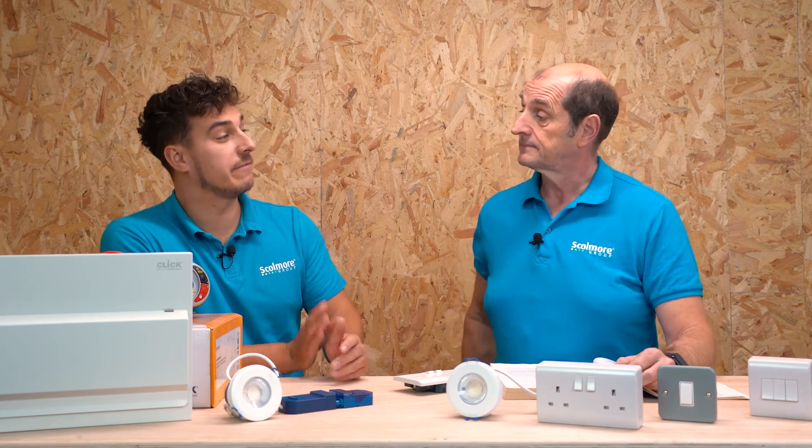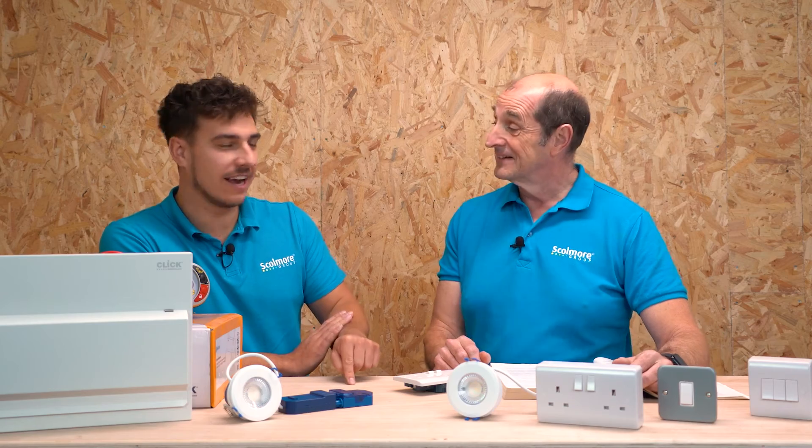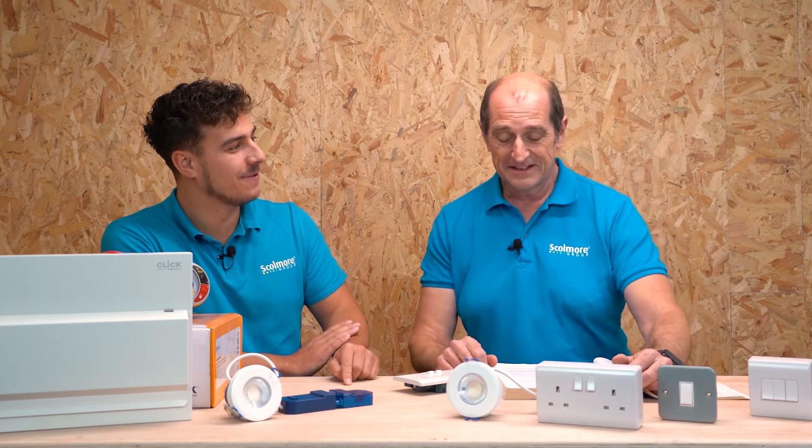My thing with it as well is that when we start to look at faults — a lot of people doing EICRs — if you've got a fault on a ring main, at least you can separate it out into two radials. If you've got a fault on a radial circuit, you are staying until you fix and find that fault.